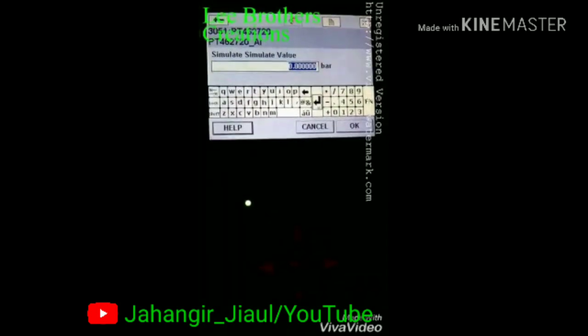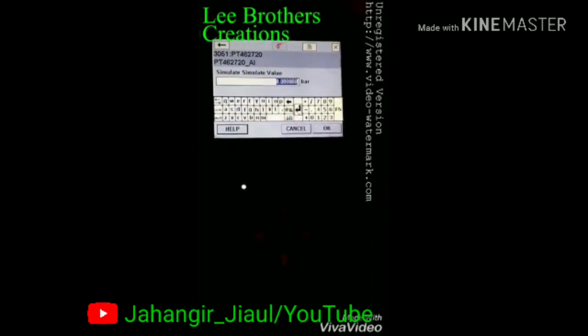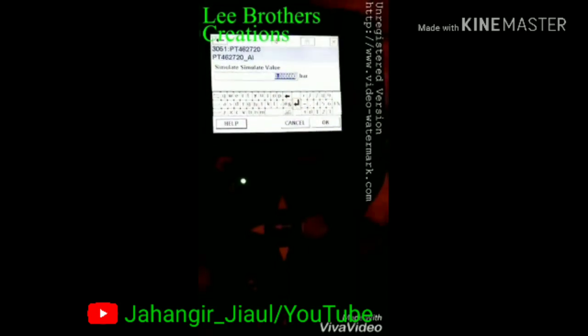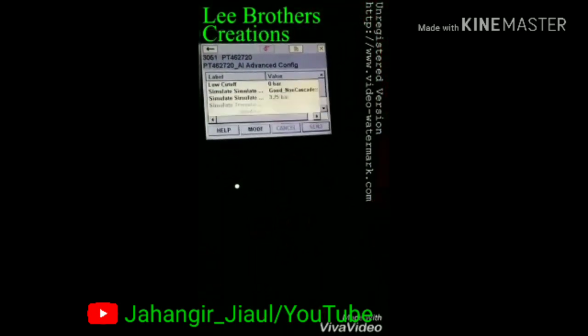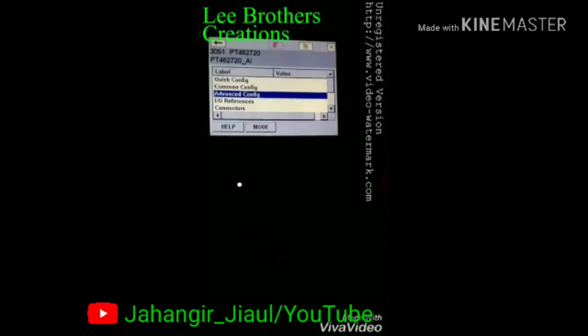We are seeing that value on the display as well as on the DCS side — the same value shows in the connected section. Come back and go to advanced config. Now I apply 25% to do the loop test. Select OK and click send. You can see the value received on the DCS side: 3.75, which corresponds to 25%.